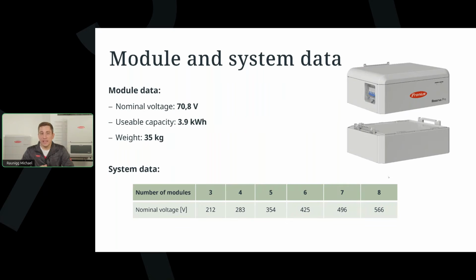The number of modules then gives you the maximum nominal voltage of the system. So that means that with the 3 modules, with the smallest systems, we are starting with 212 volts of overall system voltage. And the biggest system with 8 modules gives you a maximum voltage of 566. And as you see, especially with the Gen 24 series, where the voltage is more dependent on the overall power, that means that even with the biggest Reserva Pro, with the 566 volts, we are getting a very nice voltage and therefore nice charging and discharging power.